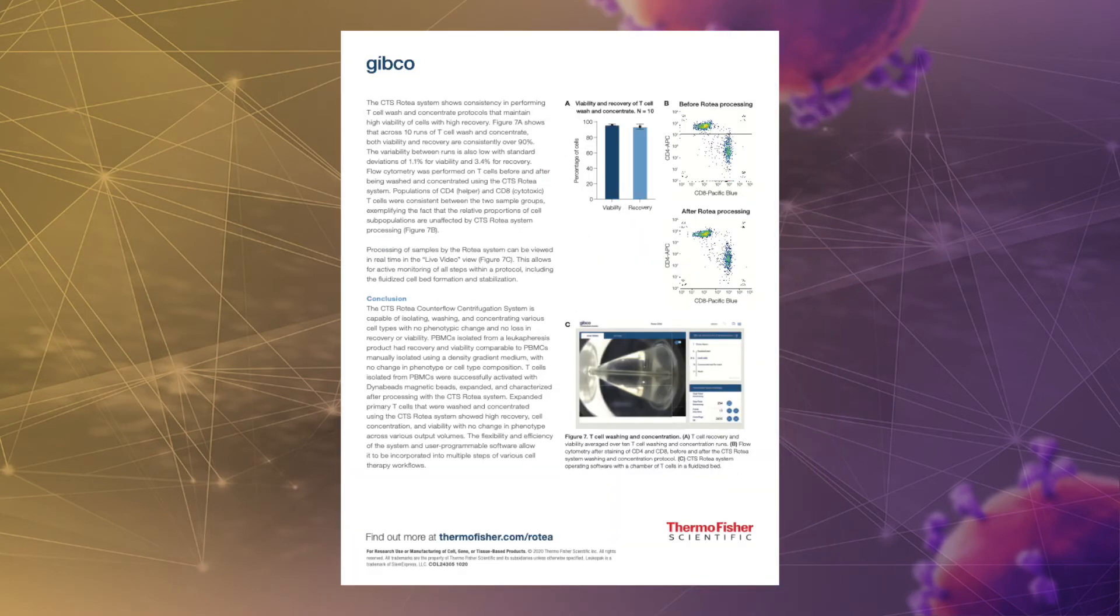Key features of the CTS-Rotea system include low output volumes, as little as 5 milliliters, as well as process flexibility, utilizing user-programmable software that enables creation and optimization of protocols. Another key aspect is high cell recovery and viability. A fluidized bed supports low shear processing, enabling greater than 95% cell recovery without decreasing cell viability.